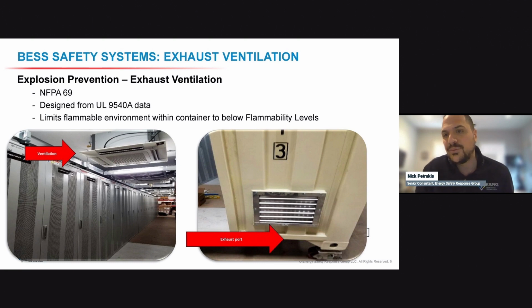Explosion protection and making sure these systems are properly installed and designed is probably one of the most critical safety components for energy storage systems. You can do it with exhaust ventilation systems that trigger on detection and vent gases out, or with weak panels that open up if there's ever an overpressure.